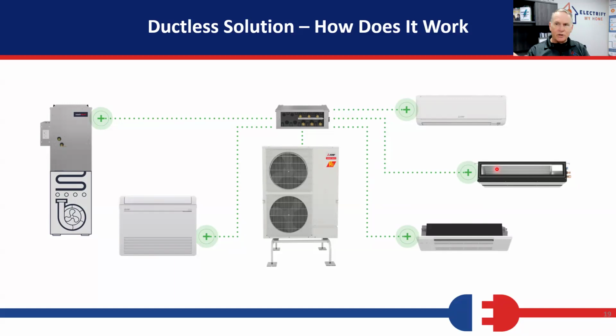So the best way, if you're going to do this, is not to go with one big outdoor unit. Maybe break it up into two smaller units. Maybe you want to do a 24 with two 12s and do an 18 with three nines or three sixes. And then I've got a much lower turn down rate, and that reduces that problem. Because if I'm trying to get efficiency and I'm saying I can run one unit at a time, it's only 6,000 BTUs, but my machine can only slow down to 20. I'm paying for 20,000 BTUs, but I only need a fraction of that. So just be careful with these. Ducted is always going to be more efficient if you do a good job, and it's going to cost less.